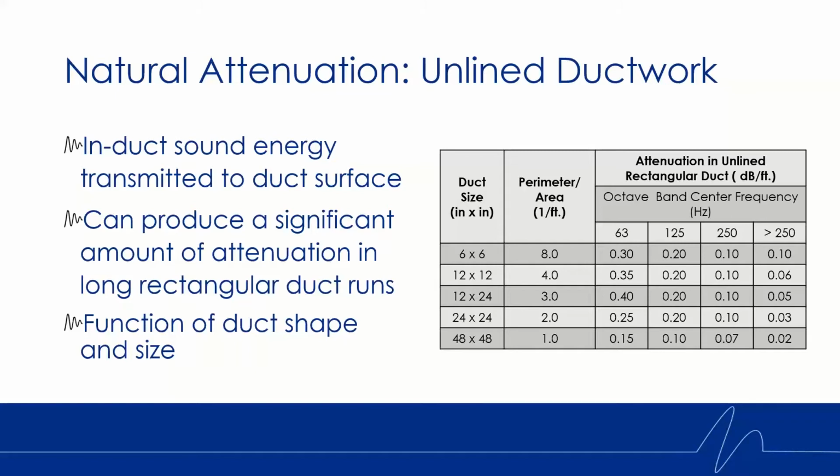Keeping in mind that you're not going to see the same thing with circular as you will with rectangular. Rectangular is going to be a lot more effective for natural attenuation than circular will, just because of how rigid a circular duct is.